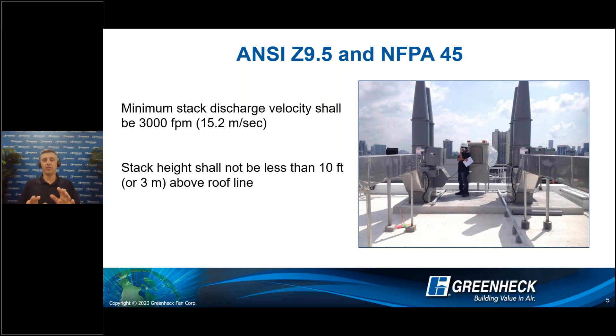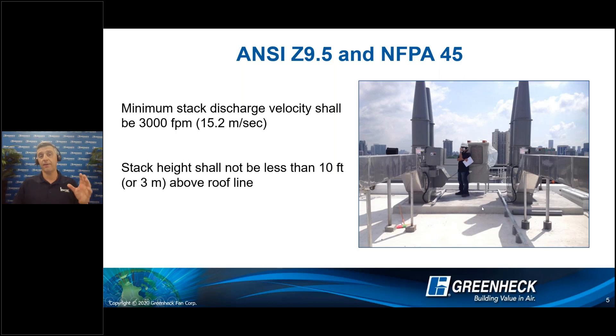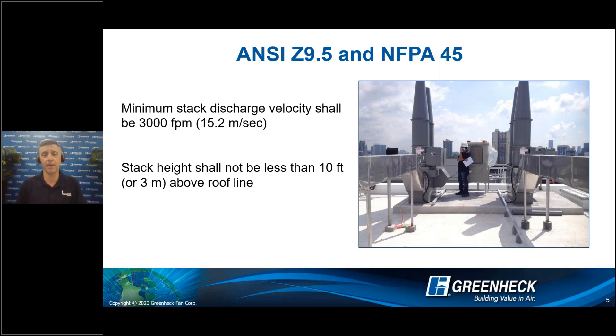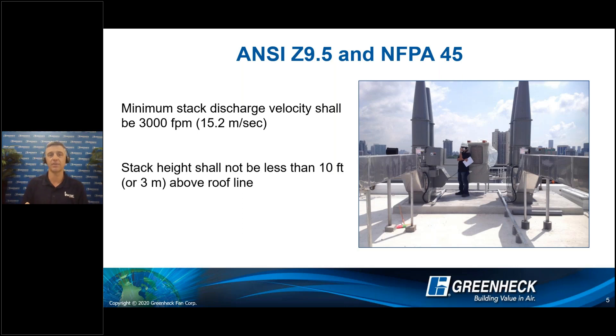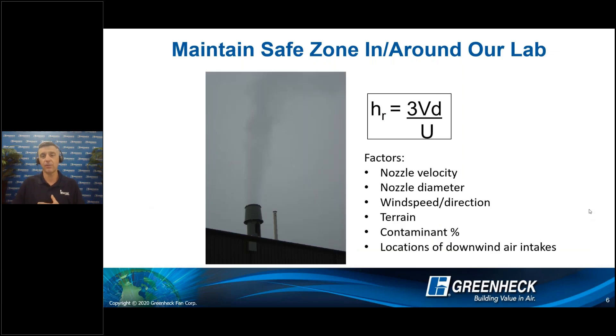A few fundamentals on the products: ANSI Z9.5 and NFPA 45 dictate a lot about the shape and look of laboratory exhaust systems. NFPA 45 talks about the height from the concrete pad to the top of the stack — the discharge needs to be 10 feet (3 meters). That keeps people from reaching into the airstream and getting into potential contaminants, and gives us a stack to get that effluent up and away from the building.